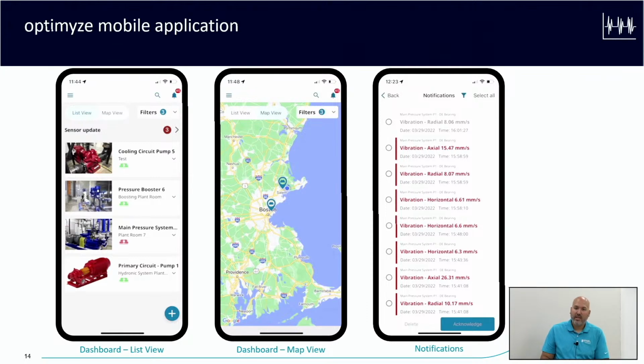It wouldn't be necessarily uncommon to have multiple sensors on a single pump. You may have one on a bearing housing, another on the motor. You're monitoring two different portions of that asset. If that's the case, you would see two sensor icons side by side next to that specific pump product there. But something I like to point out, everything on this is traffic light indicators. So what I mean by that is if you're seeing sensors that are green, that means everything is good. If you're seeing sensors that are yellow, which is some sort of alarm, or red, which is a more critical error, then that means that there's some sort of issue.